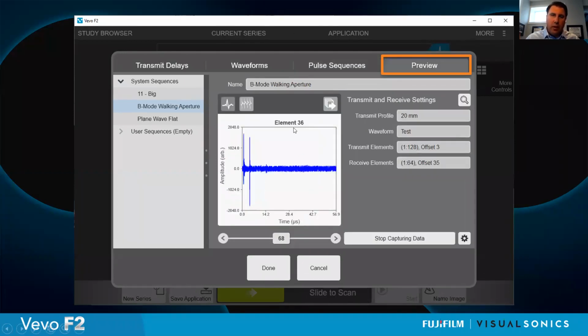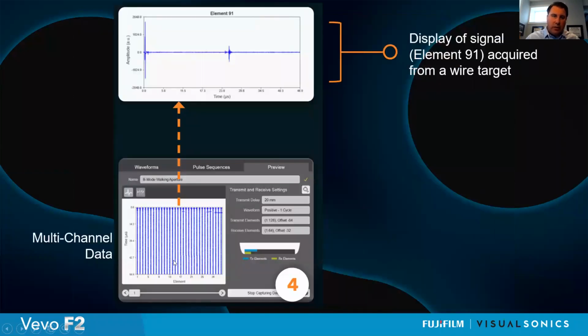Here's an example looking on element 36 of the array. This is just from a wire target. And then you can also start to look across all of your elements. And we see here, this is an example of element 91, again, collected from a wire target. You can see the echo off the wire target. So again, very much like an oscilloscope at this stage, which allows you to get very, very deep into the data and see what's going on at a channel level.